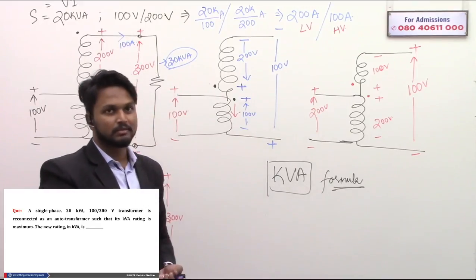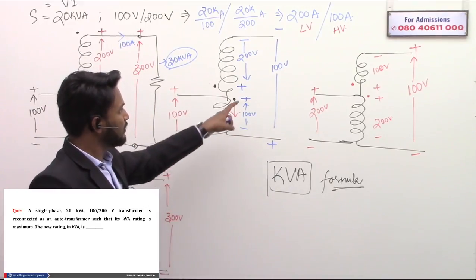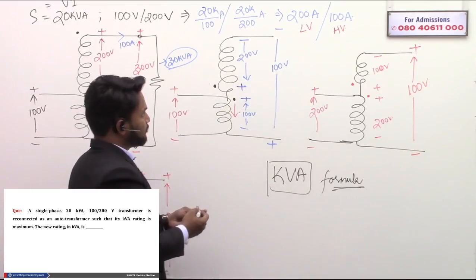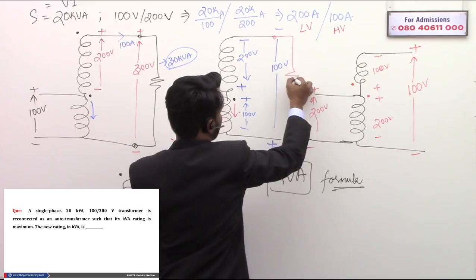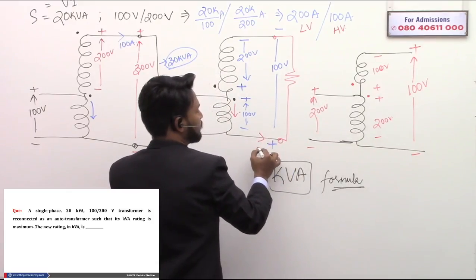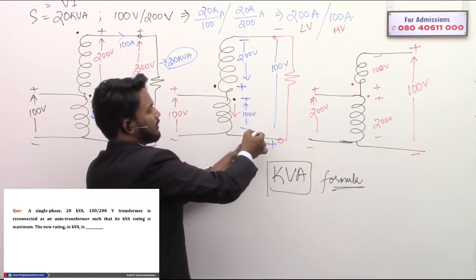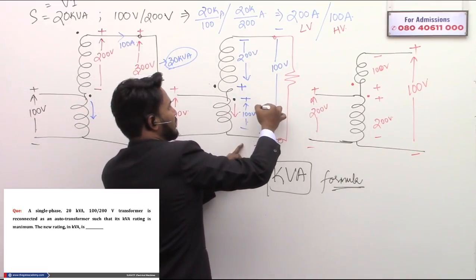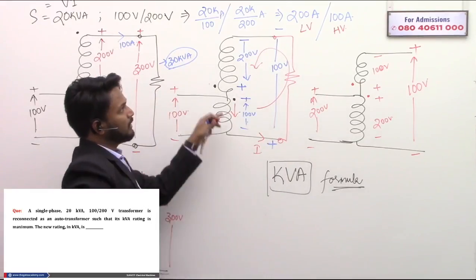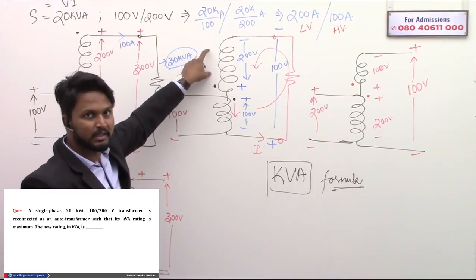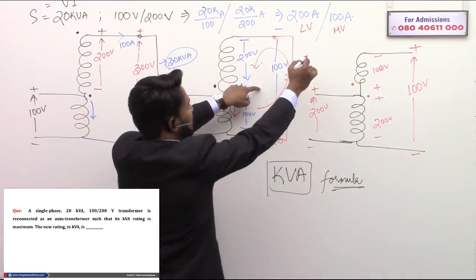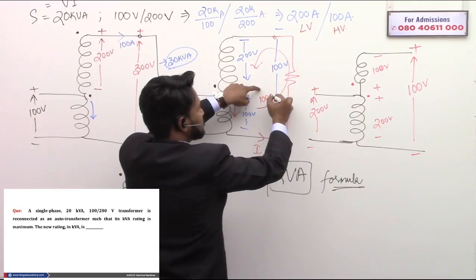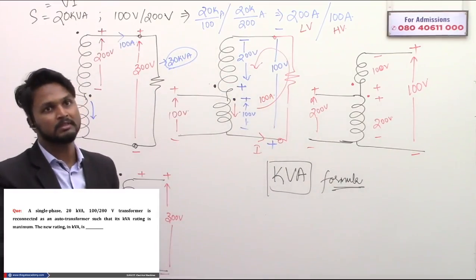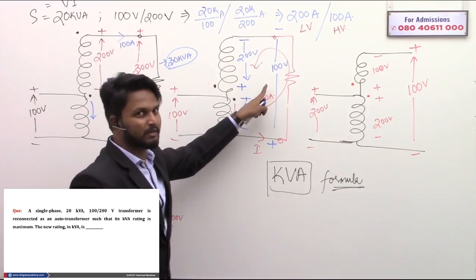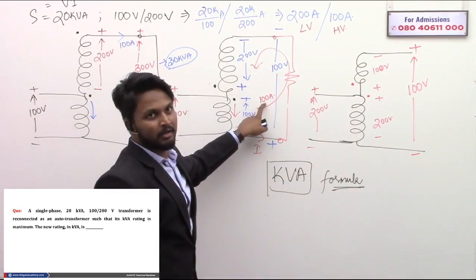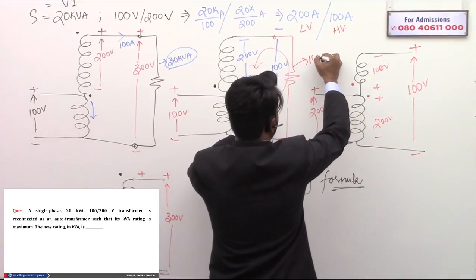Rating of the second configuration. Just look at this rating of the second configuration. The output voltage is 100 volts, right? If you connect an external load, you can drive a current of maximum. See, the current is flowing in this manner, right? How much current can be flown through this HV winding? A current of 100 amperes at maximum can be flown through this particular HV winding. Therefore, the rating of this particular configuration is 100 volts multiplied by 100 amperes. Rating of this configuration is 10 kVA.